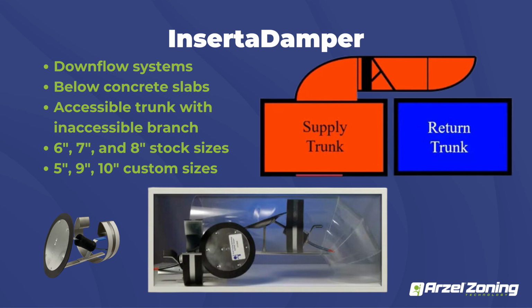One of the best uses that I would use this damper for when I was in the field is just like the picture above. If you had a top-loaded boot that goes right over your top of your return, and it's a really short run where it doesn't go past your return duct, typically you're going to have to either remove that return duct, install your damper, reinstall the return duct, and if there's ever a failure, you're going to have to pull all that back apart again to get to that damper.